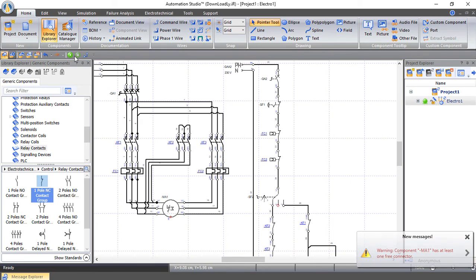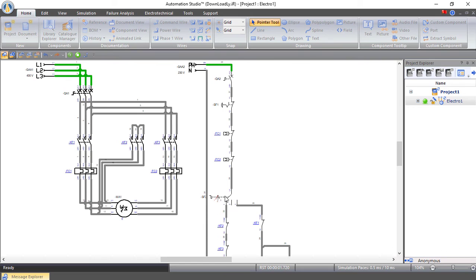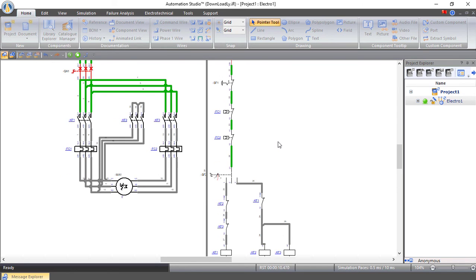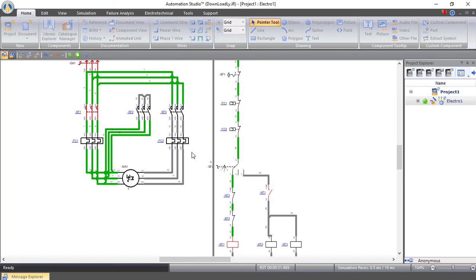Now let's simulate our circuit. Let's put the position to 0. Now let's close the circuit breakers, and as you can see, nothing will happen. Now if we connect this switch as delta, this will make this motor work in the low speed. And as you can see now, it's working, but in the low speed. Now let's open this circuit.